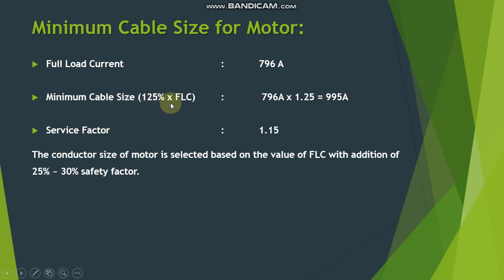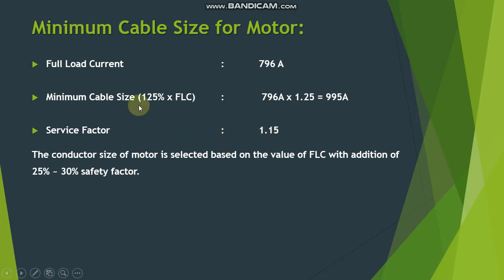Here we are taking 25%, so adding the safety factor to the full load current gives us 995 amperes. The service factor for this motor is 1.15, meaning the motor can withstand 15% overload condition. This service factor is incorporated into our 125% safety factor, so we don't need to add any extra factor on top. Now we have the full load current as well as the minimum cable size of 995 amperes.